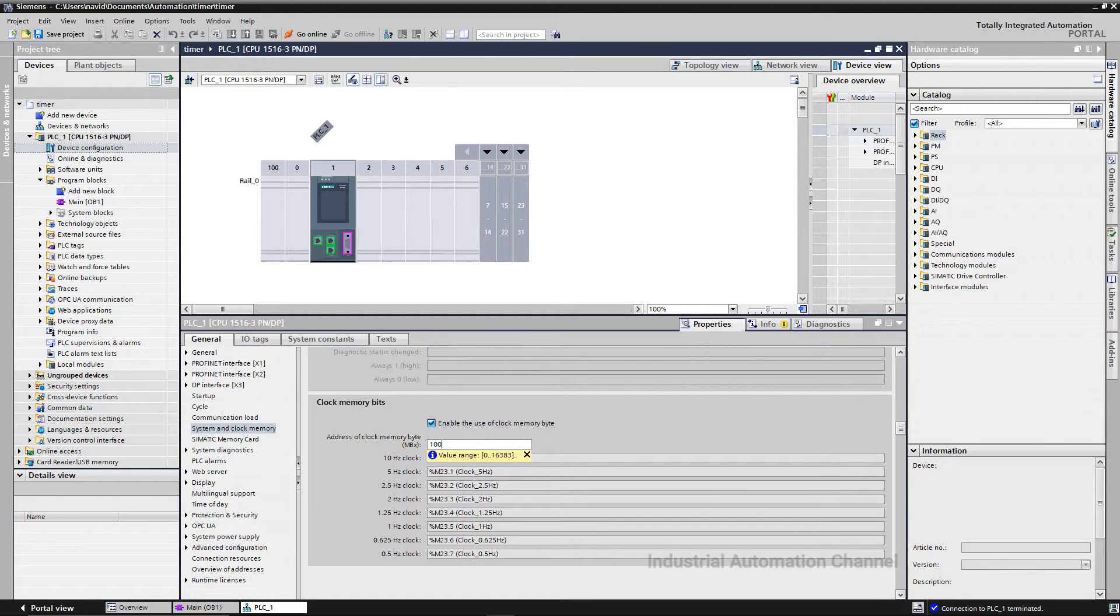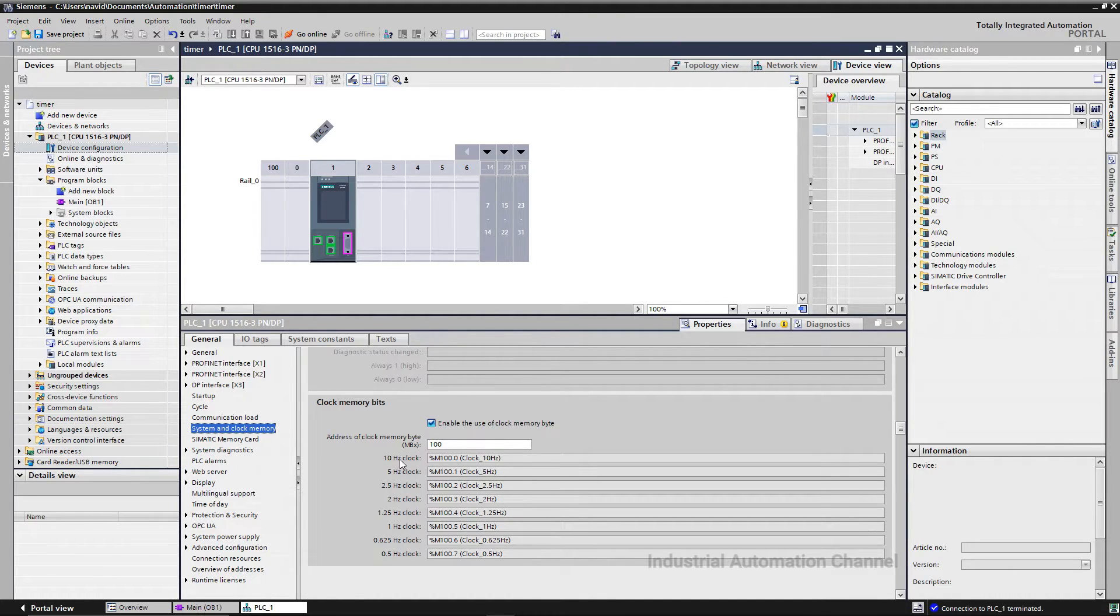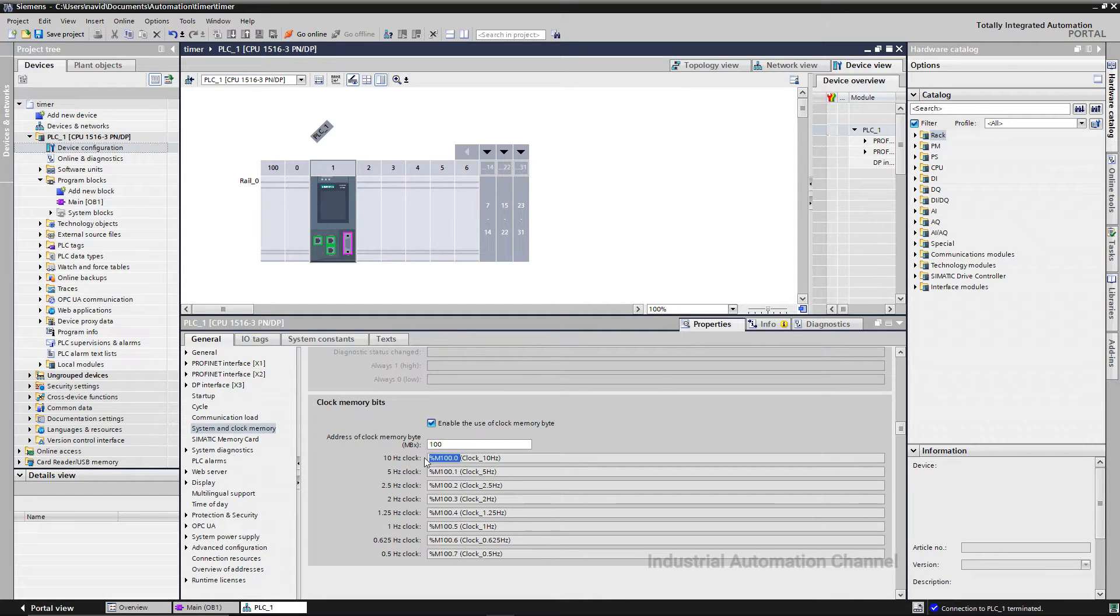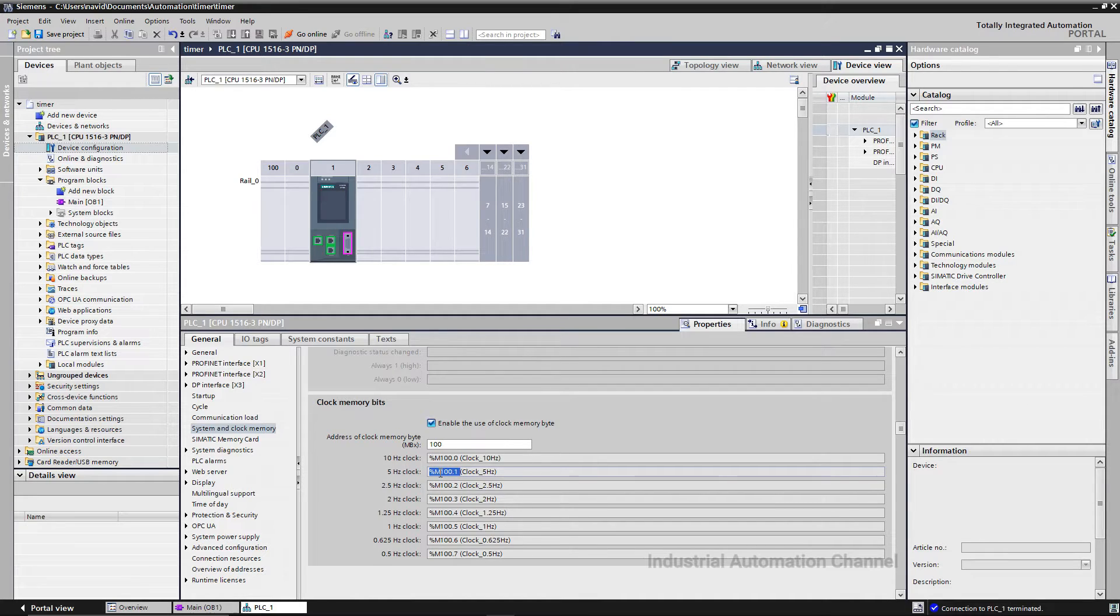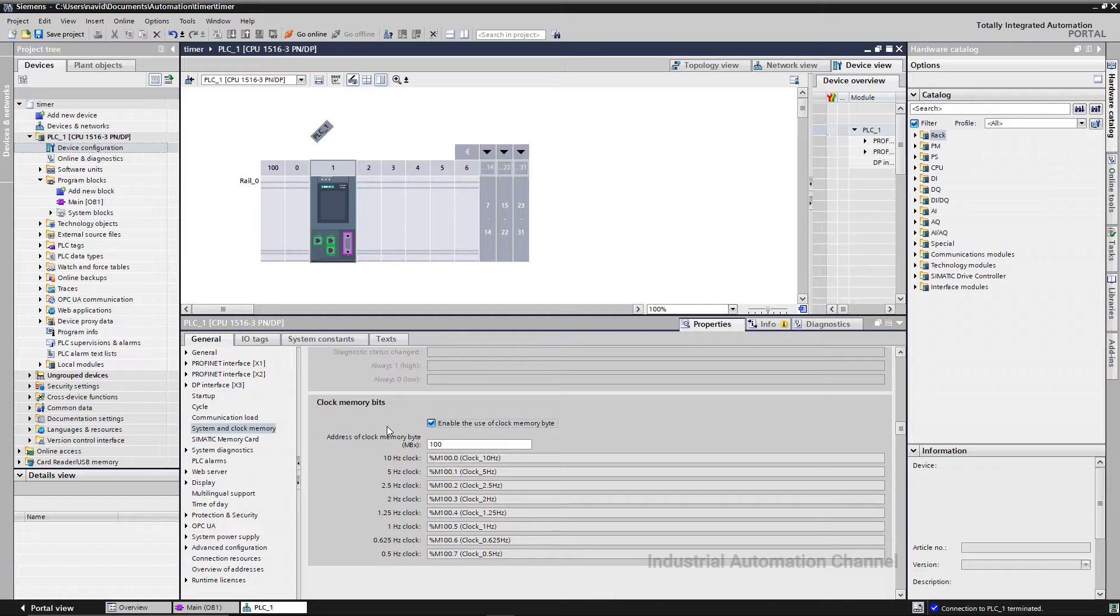I use byte 100. Press enter. Now you can see that we have a 10 Hz frequency at bit memory 100.0. It means this bit will be on and off 10 times per second. 5 Hz at M100.1, 5 times on and off at memory 100.1, and so on.